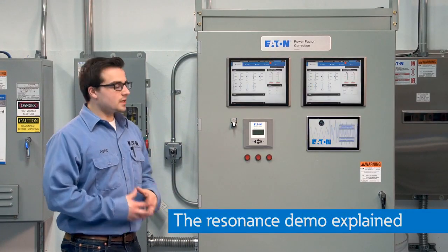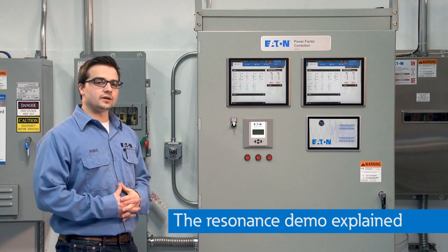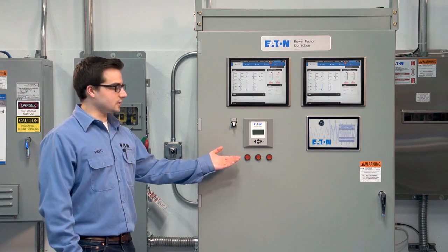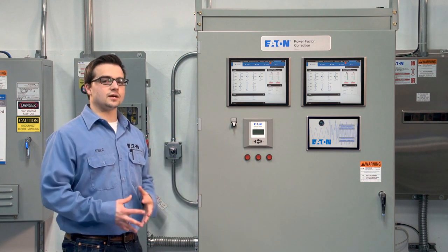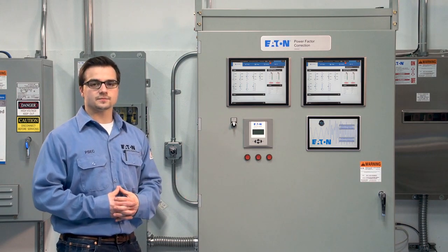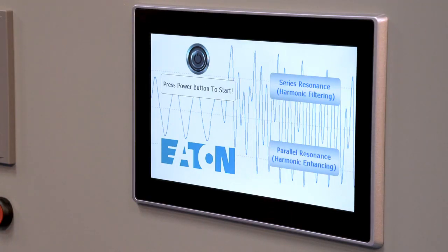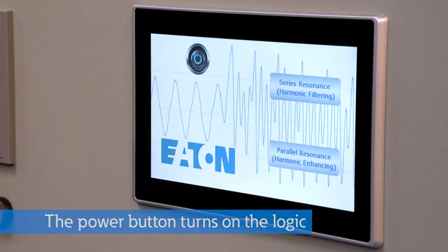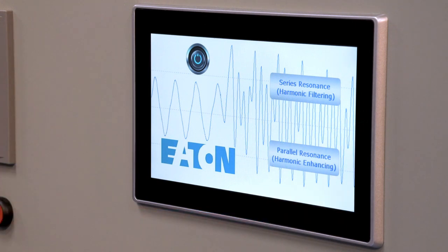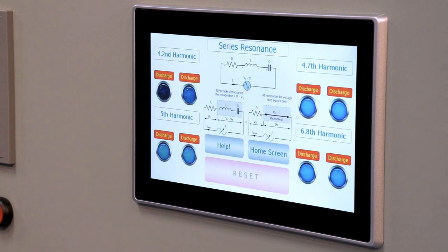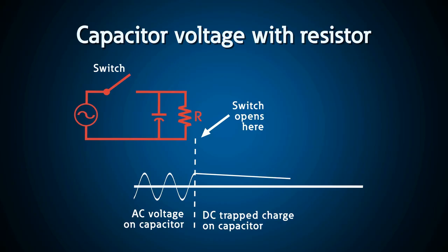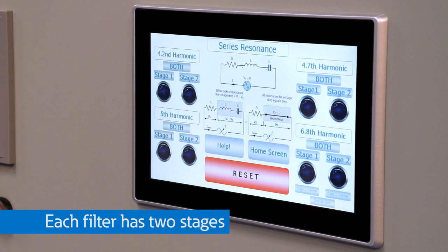So here we have the resonance demo. Up top we have HMIs displaying all of our metering information. Here is the switch that turns the system on — it also switches between automatic controls in the Autovar 600 and the PLC we have programmed to do the different types of filtering. This is the home screen for the resonance demo PLC. Here we have an example of harmonic resonance as our background, our power button to engage our logic, and our two choices: series resonance for harmonic filtering and parallel resonance for harmonic enhancing. I'm going to choose series resonance. We're going to notice now there's a discharge on all of the stages — this is making sure that any capacitors that are charged will fully discharge before switching them back onto the bus for safety.